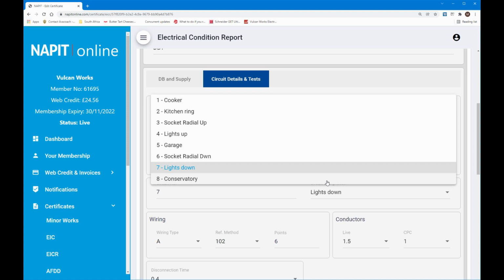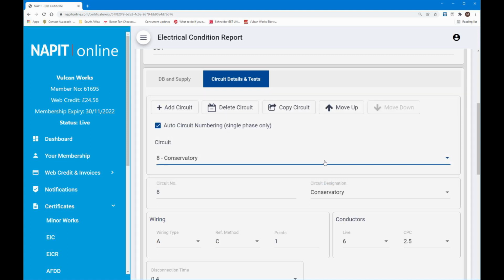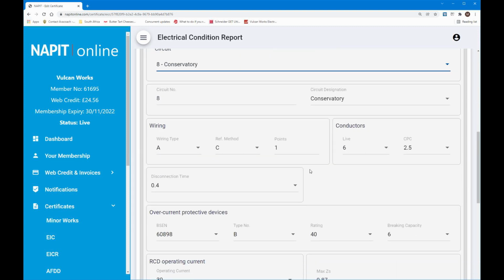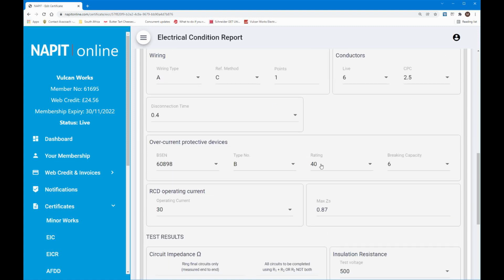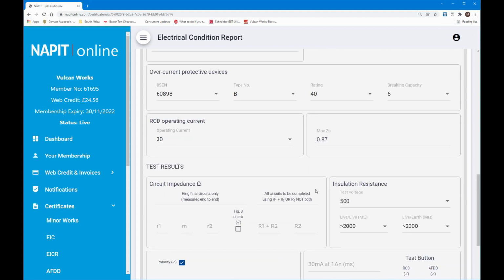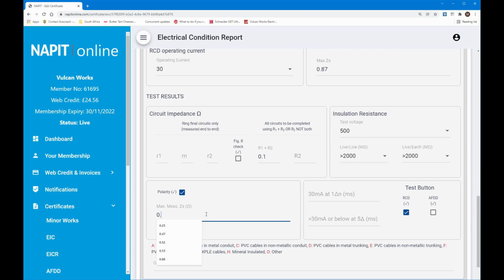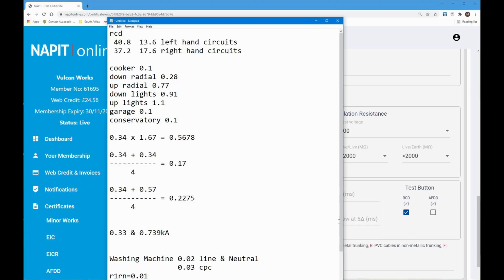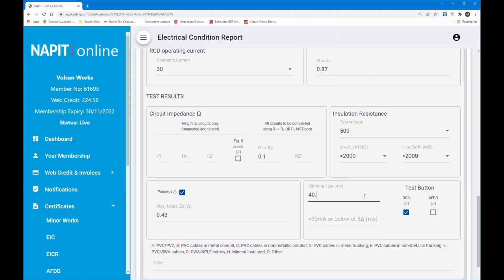And finally, the last one is the Conservatory, which is the line going to the Conservatory DB board, and type A wiring, so it's twin and earth. It's clipped direct to that one, so it's a different reference method, reference method C, and only 1 point because it's going directly to that other consumer board. It's done in 6mm with a 2.5mm CPC. It's on a 40 amp breaker, so it's got a maximum ZS of 0.87, and the reading I got from that was 0.1, which gives me a value of 0.43. Again, I was able to do an insulation resistance test on it, and it was absolutely fine. And as with all the others, it was a 40.8 and a 13.6 on the RCD.